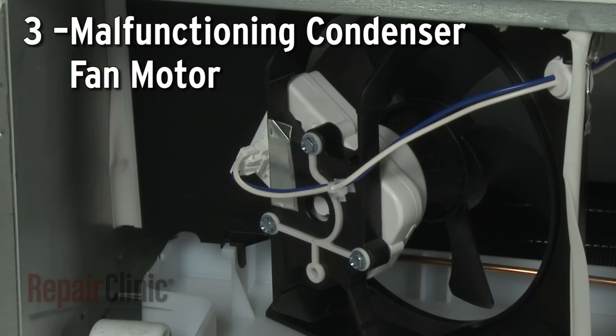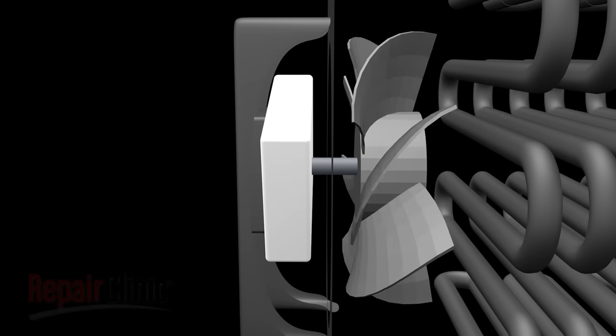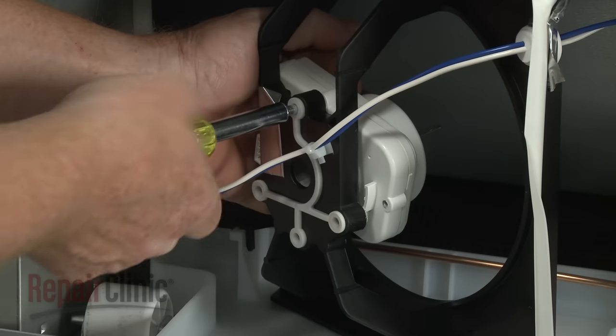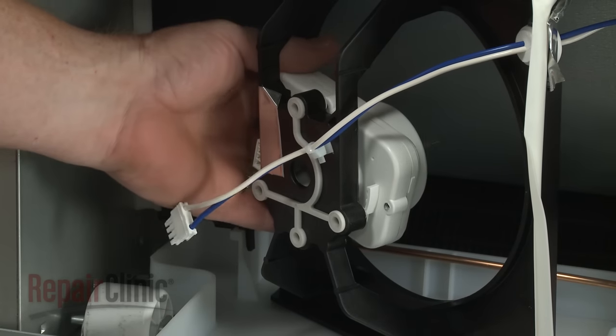As with the evaporator fan motor, the bearings in the condenser fan motor may be defective, resulting in a grinding sound. Again, the malfunctioning motor should be replaced.